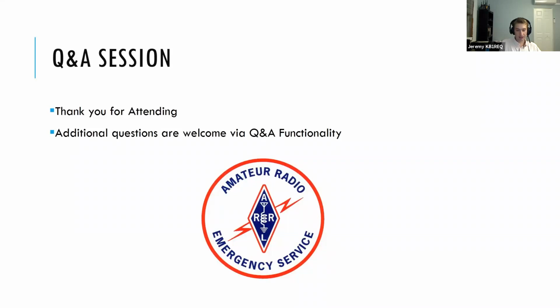And that's often the sign that, okay, it's not burned up. It wasn't a very high current device, but a strike, excuse me, or surge event, but there was enough to damage, especially things like microprocessor silicon devices that are very sensitive. Mitigating that is the same steps we talked about here, because it's going to be a high transitory voltage, even if it's not high enough to burn the stuff. It's higher than it should be there, and it's what would be over the threshold voltage of a normal surge suppression device. So all the surge suppression practices we talked about prevent a wide range of events, from our more damaging direct surges to those caused by induced voltage.